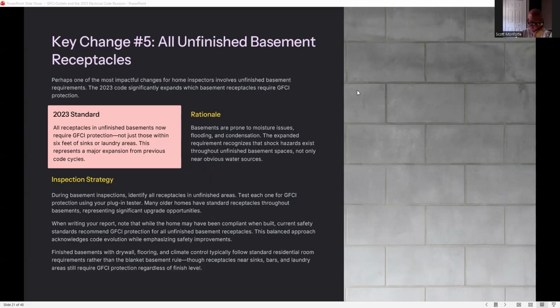For your inspection strategy, during basement inspection, identify all receptacles in unfinished areas. Test each one for GFCI protection using your plug-in tester. Many older homes have standard receptacles throughout the basement, representing significant upgrade opportunities. When writing your report, note that while the home may have been compliant when built, current safety standards recommend GFCI protection for all unfinished basement receptacles. This balanced approach acknowledges code evolution while emphasizing safety improvements.